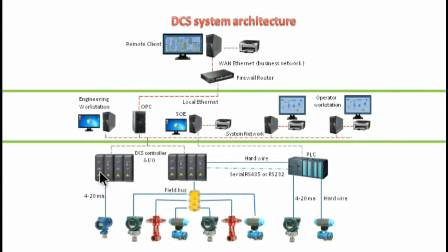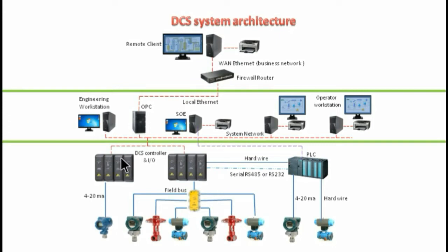The IOs and controllers will get signals from the field devices. This can be through conventional 4 to 20 milliamps or through the field bus network. The controllers will be connected to the system network, which is normally proprietary to the DCS in use. The engineering workstation will be used to configure the controllers and for troubleshooting. The DCS controllers are mainly used to handle continuous process control with many PID control loops and can be configured with different control algorithms to keep the plant running.